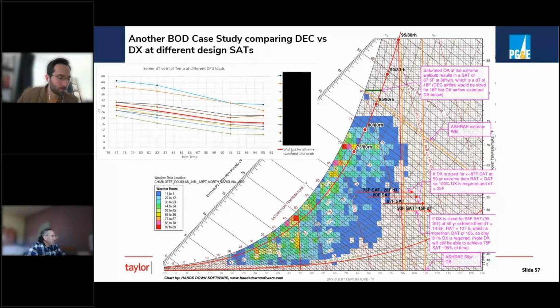So you can see, if we were to supply 77 degree or lower temperature, the average delta T across the equipment was 28 degrees. And then if we supplied warmer temperature, say 91 degrees, then the average delta T across that equipment was going to be less than 20 degrees. And we went through this exercise to optimize the design based on the fact that we'd need more air if we were going to design it around a higher temperature, or less air if we were going to design it around a lower temperature.